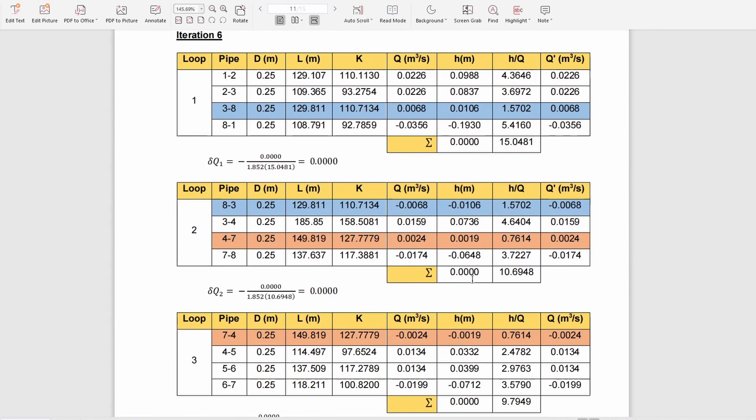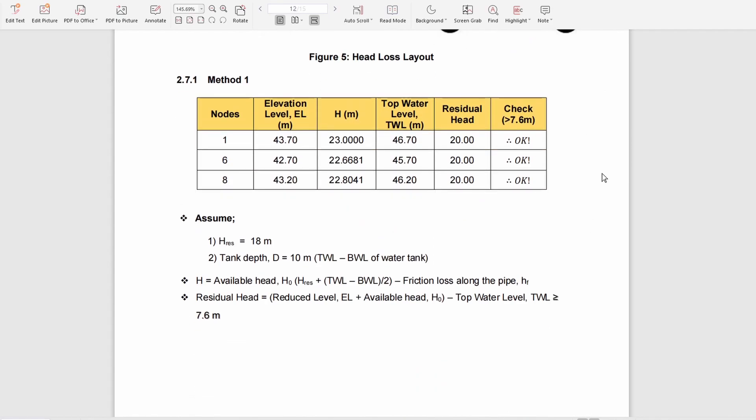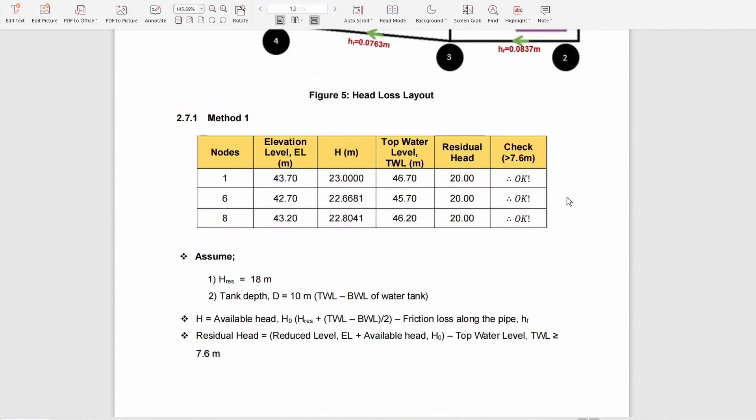Next, we move on to the residual head. You put the loss obtained from iteration six and identify the residual head using the formula shown. We check whether it is greater than 7.6 meters. Since it is greater than 7.6 meters, our design is accepted.